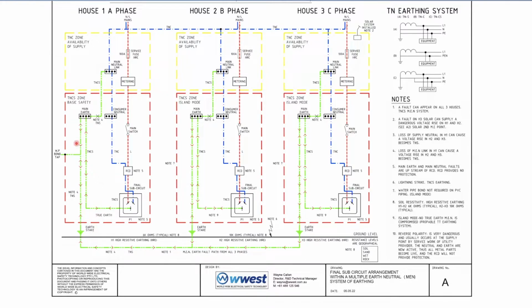Obviously then in the final subcircuits, we've got this one that comes down to your earth point on your final subcircuit. So we look over here at house 2, and it's slightly different. We've got our mains coming in at the top. I've got the red active going all the way through the service fuse down to the final subcircuit with the power point, through the RCD and everything like that.